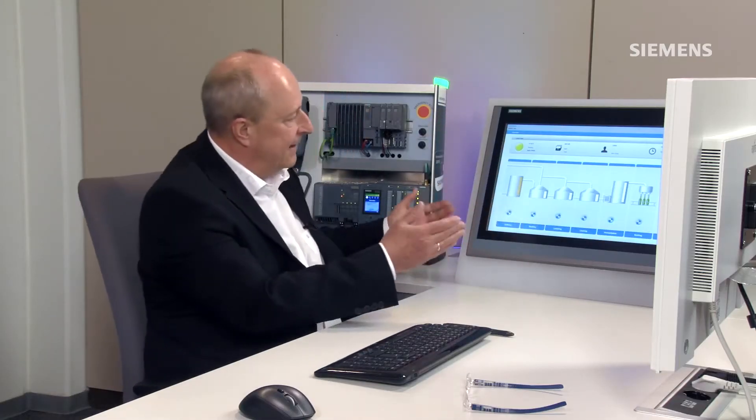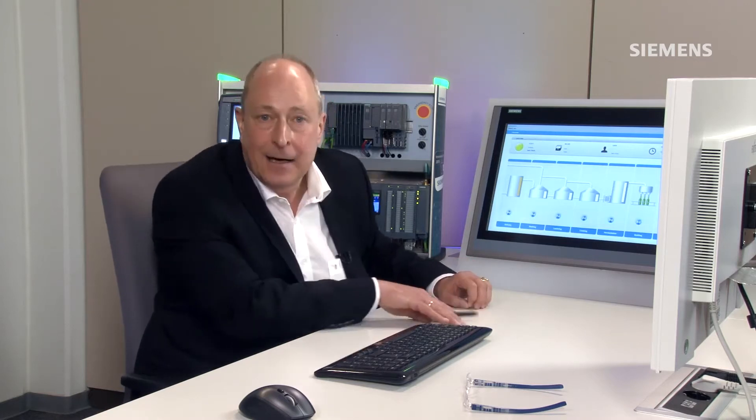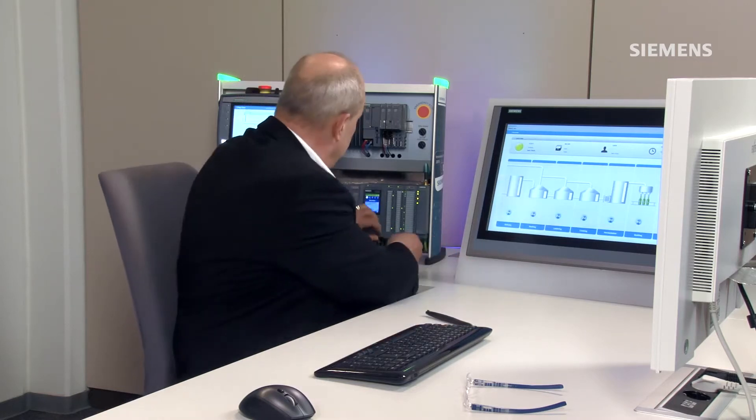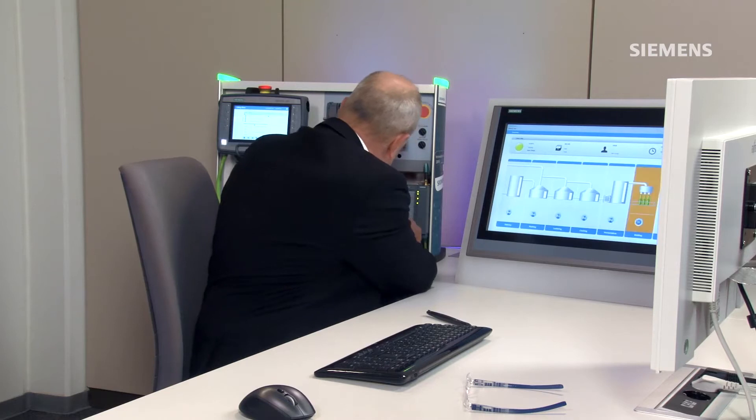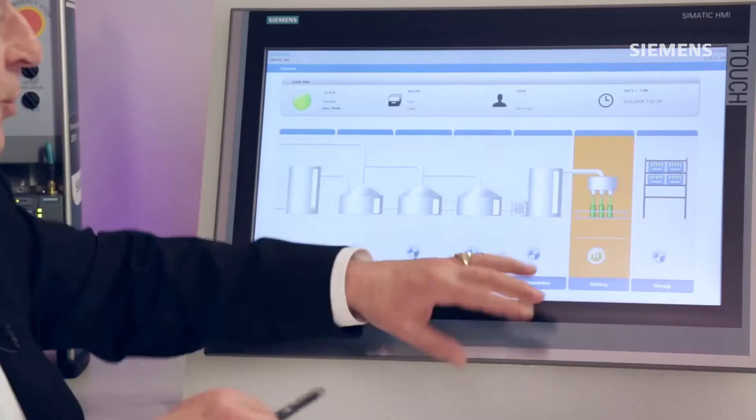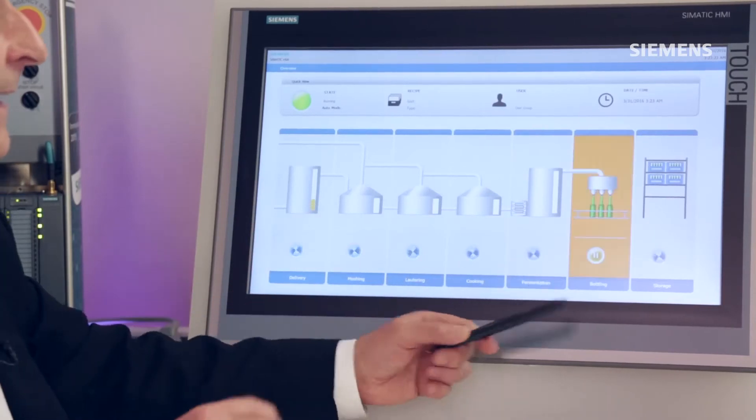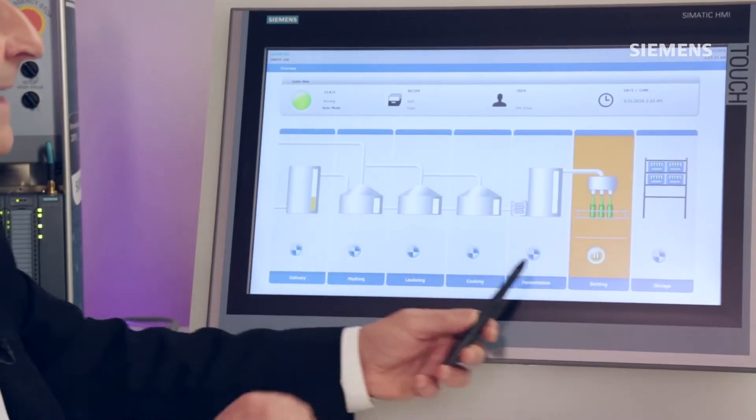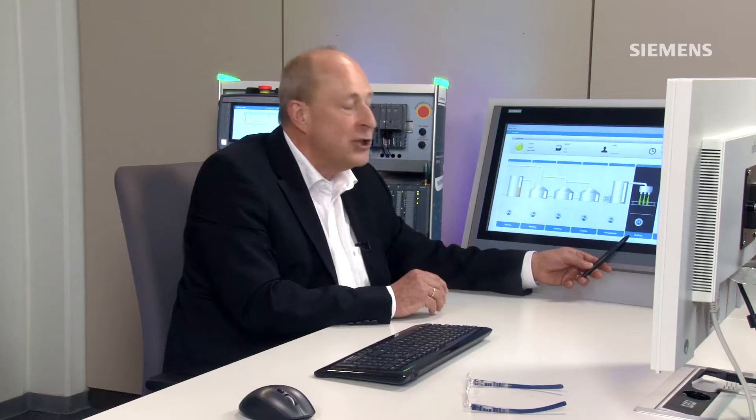You can see here how individual sub-processes are all functioning smoothly and correctly. I'll now simulate a fault by manipulating an input. I've now manipulated an input and as you can see, an overview display already indicates that something is wrong in this particular subset of my bottling process.